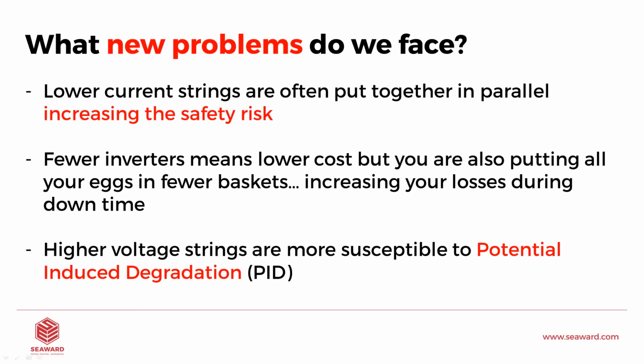Also, another issue that we're facing, and not relating to test equipment, is that fewer inverters mean we're lowering the cost, but we're actually putting all of our eggs in fewer baskets. So this means if one inverter goes down, we lose a lot more generation than on a 1000 volt system. So this is something to be aware of when we are designing our PV systems. Also, higher voltage strings are more susceptible to the dreaded PID, and I'll cover that a little bit more on the next slide. And this is something we really need to be aware of.